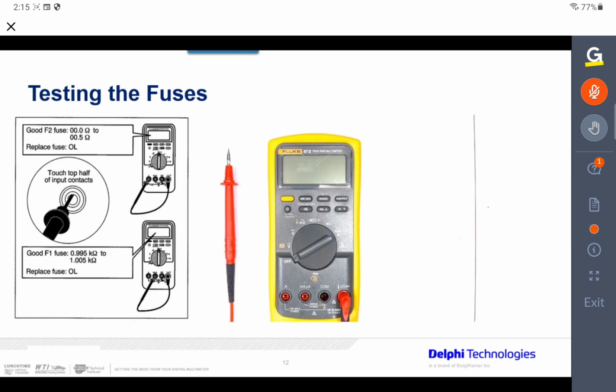So it says good F2 fuse. It should be on the sides over there, 0.00 ohms to 0.5 ohms. That's checking that fuse. All right, that's the high fuse. If I check my other fuse, it's on the milliamp fuse, it should be 0.995 kilo ohms to 1.005 kilo ohms. So let's check this meter, see if it's okay.